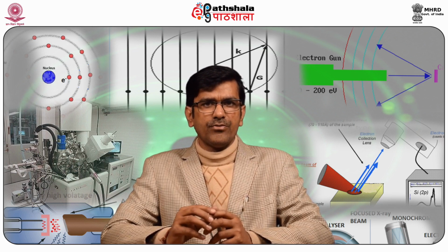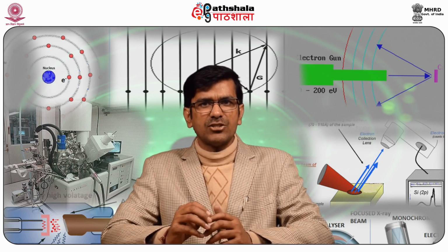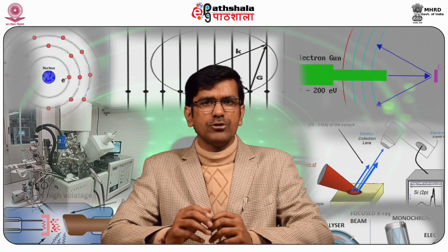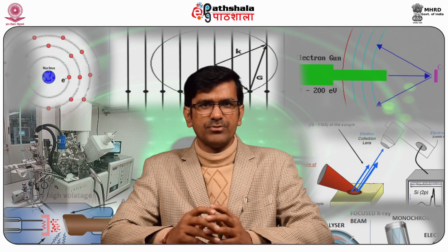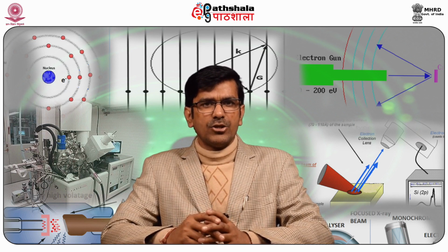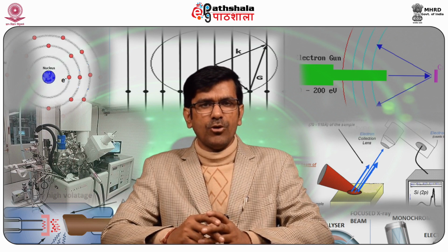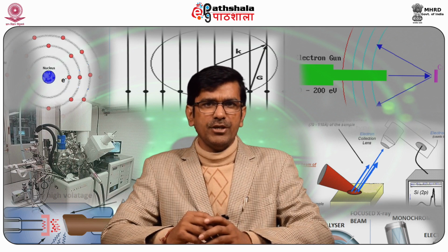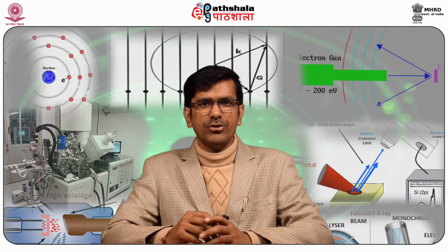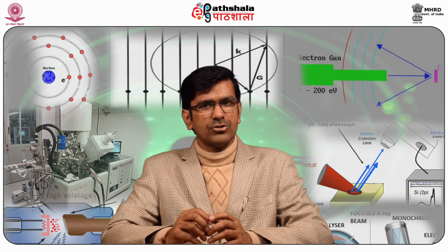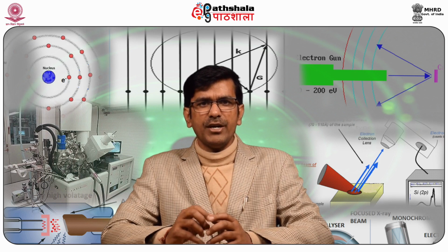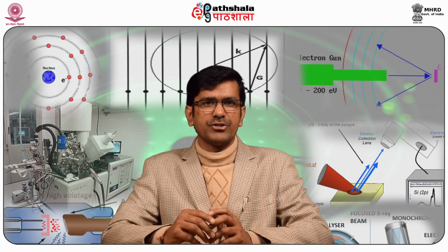In the analysis chamber, the vacuum level gets down to 5 × 10^-10 torr, which is equivalent to about 10^10 molecules per liter. So it is a very low concentration, while air has 2.7 × 10^22 molecules per liter. Under these vacuum conditions, the possibility of a secondary ion hitting a gas molecule within the instrument is almost zero. It is an important requirement for the analysis as the instrument is kept under ultra-high vacuum conditions.